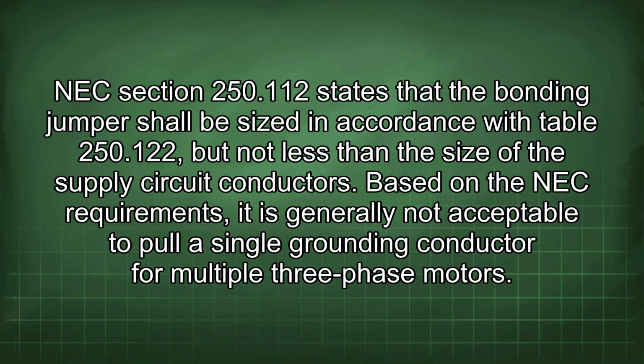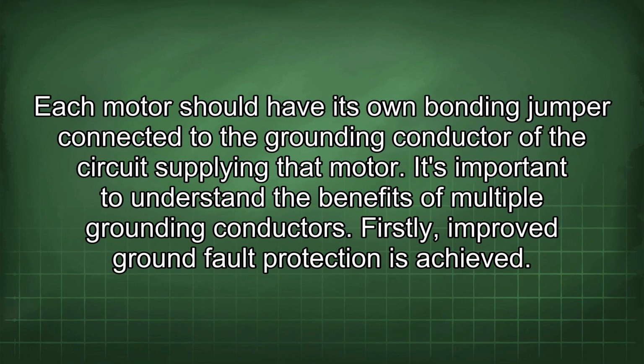NEC Section 250.112 states that the bonding jumper shall be sized in accordance with Table 250.122, but not less than the size of the supply circuit conductors. Based on the NEC requirements, it is generally not acceptable to pull a single grounding conductor for multiple three-phase motors. Each motor should have its own bonding jumper connected to the grounding conductor of the circuit supplying that motor.